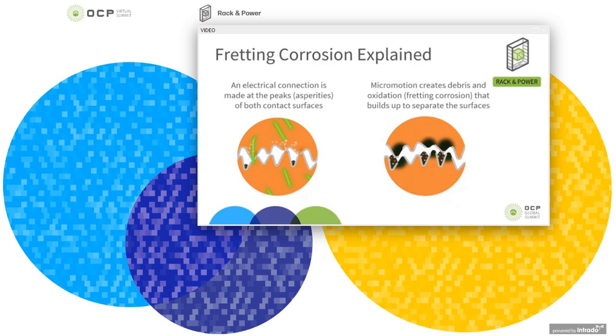Now I'm going to hand it over to Brian, and he can talk about some of his test results. Here we want to explain to everybody exactly what fretting corrosion is. A lot of people understand that an electrical connection is made at the peaks of the contact surfaces, or the asperities of the contact surfaces, as we show in the left-hand illustration. But a lot of people don't understand about fretting, where micromotion creates debris and oxidation, and then that oxidation builds up and separates the surfaces so the peaks can't meet. And so that's where you get an open connection.